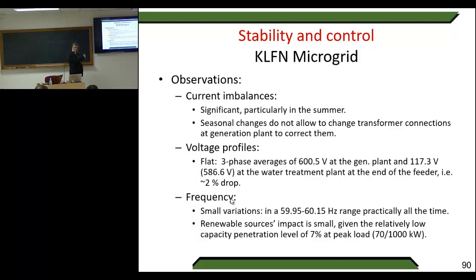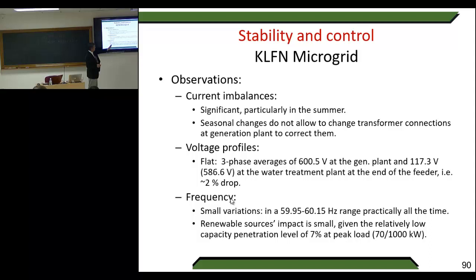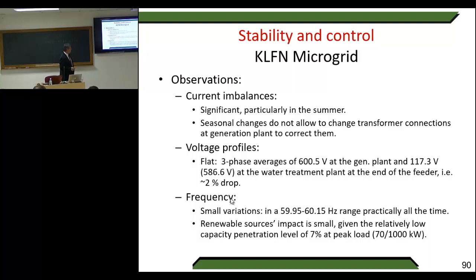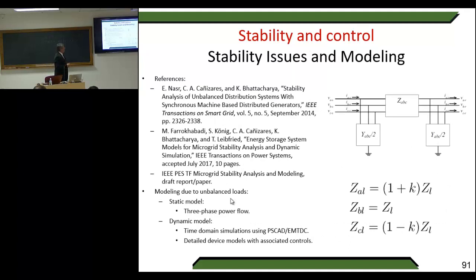The voltage profiles are flat with no big variation. Frequency shows small variations between about 59.95 and 60.15 Hz — impressive and good compared with our Guatacondo results. The impact of renewable sources is small given the relatively low capacity penetration, at about 7% of peak load. The system never goes fully renewable, but it is a very interesting reference case.